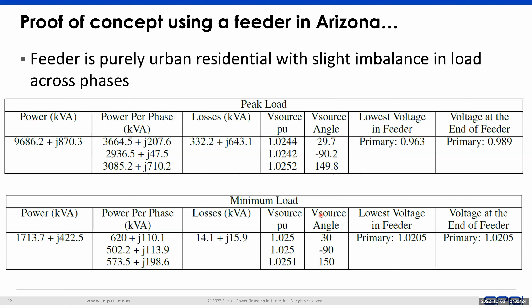Since it's primarily residential, we assumed there would only be single phase DERs on this feeder, no three phase DERs. We also assumed each home would add a rooftop PV rated around 50% of their peak load. That brought the total DER to 50% of peak load during peak loading condition, and 282% of the load during minimum load condition.